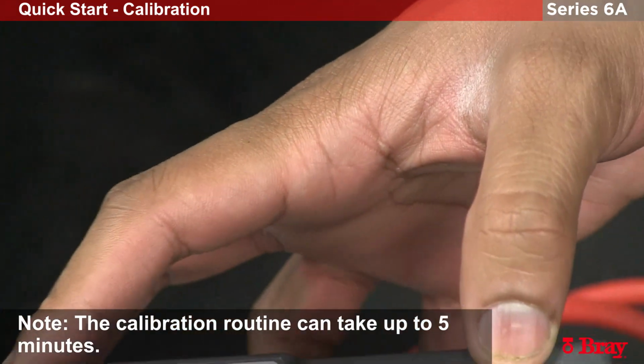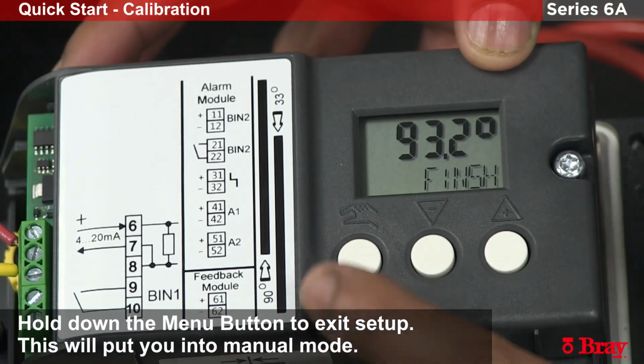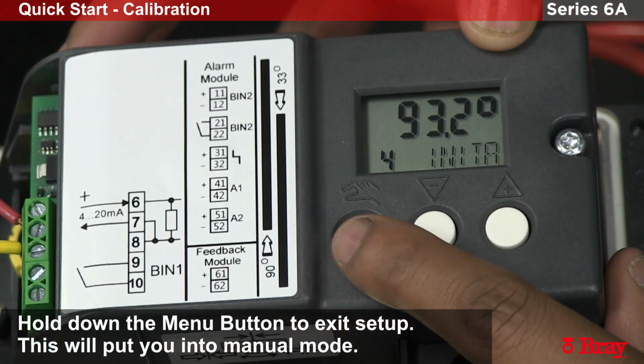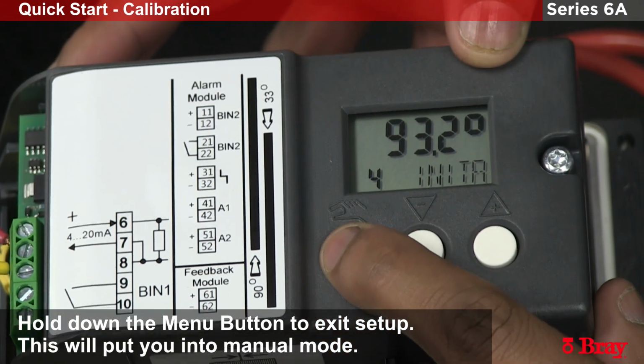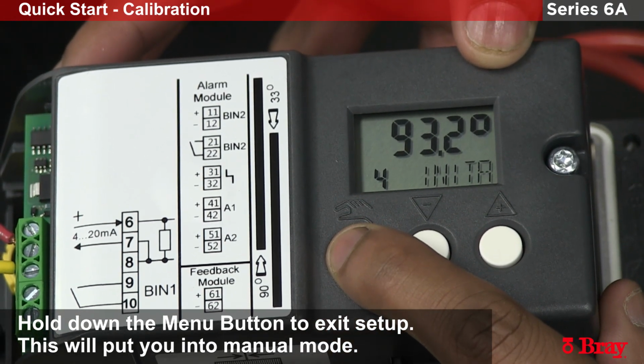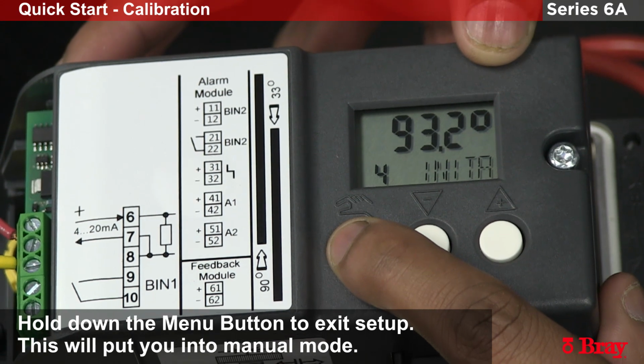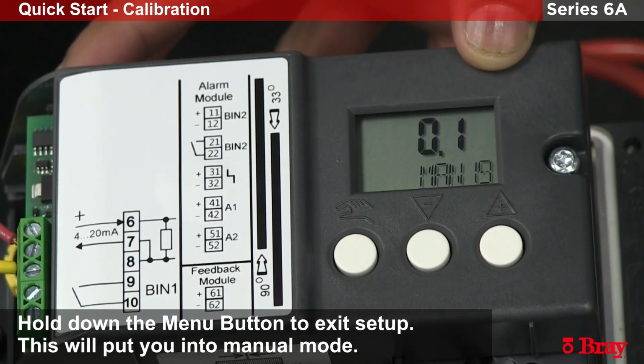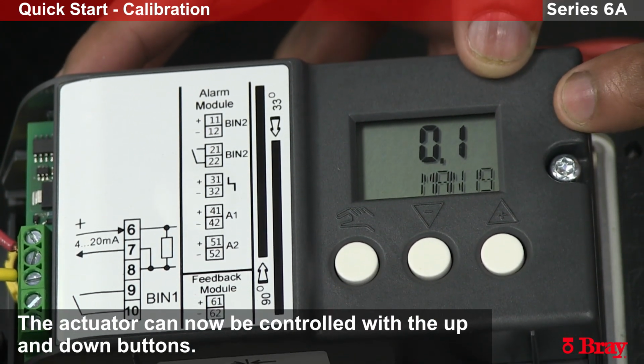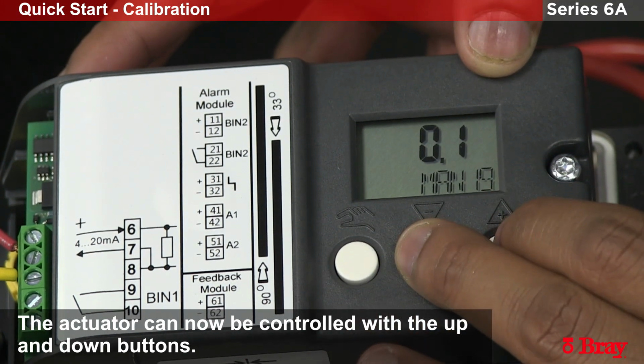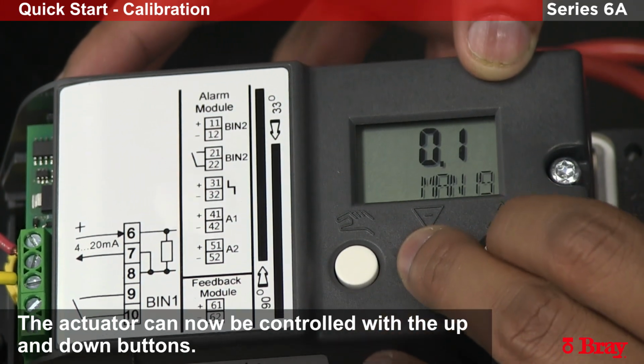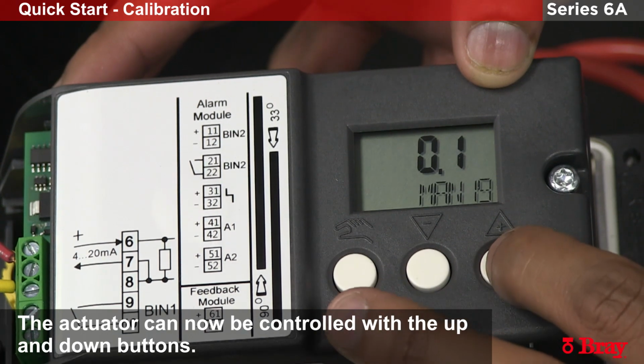When the calibration is finished, it'll state finished on the bottom of the screen. We'll hit the hand button to get out of the window. Hold down the hand button to get out of the setup windows. The unit will now spit you out into manual mode, which will let you use the up-down arrows to control the actuator. So this would be for close, minus, plus to open.